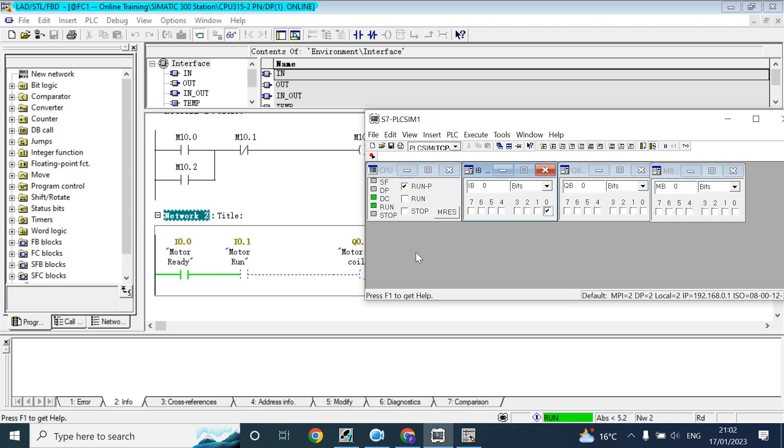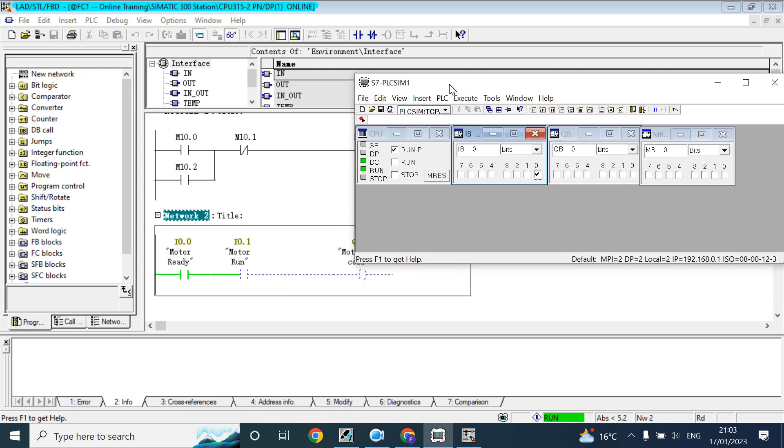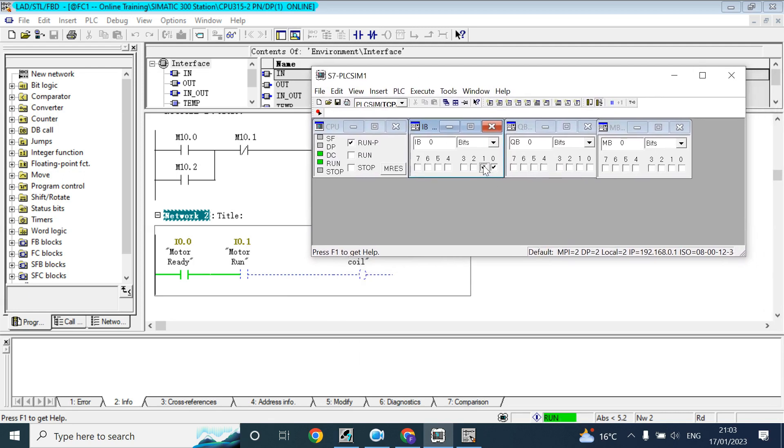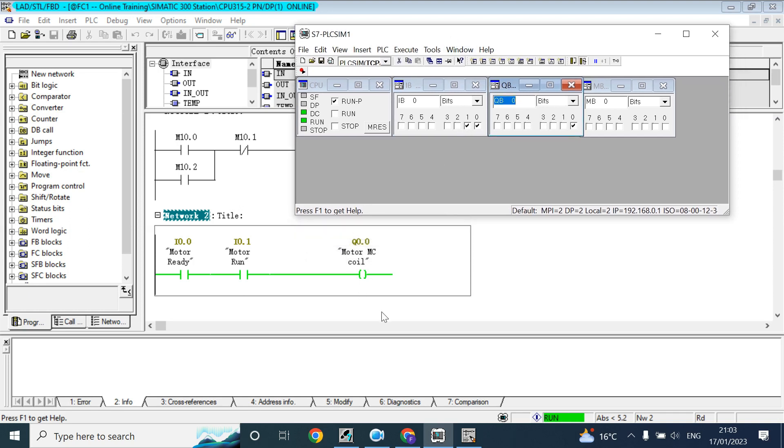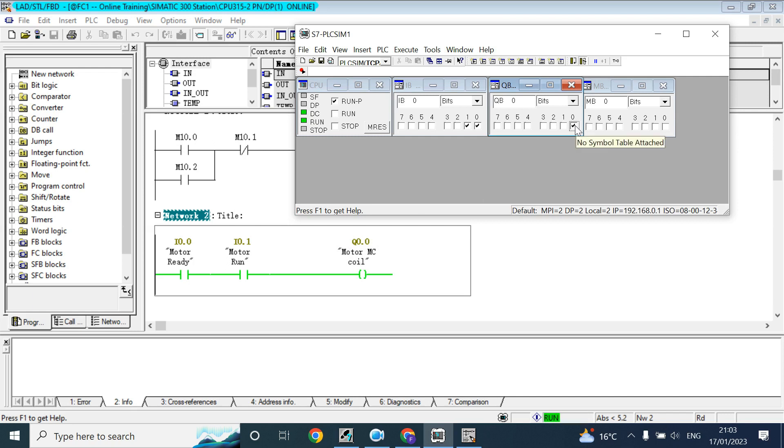See when I give a checkmark here it will be true, means it is coming from the field, but this is the simulation software. So we have clicked on that 0 bit, it is like coming from the field. And this is the motor run coil here. See it is now QB 0, which means it is byte number 0, bit number 0. That's why it is tick mark. We cannot remove it because it is written by the program and it is just monitoring.